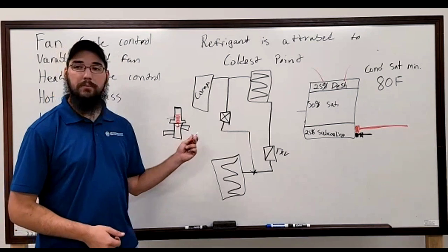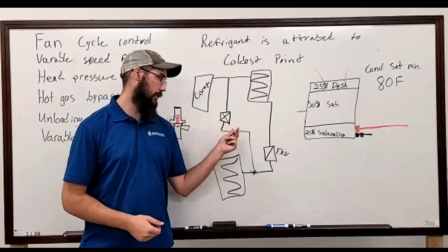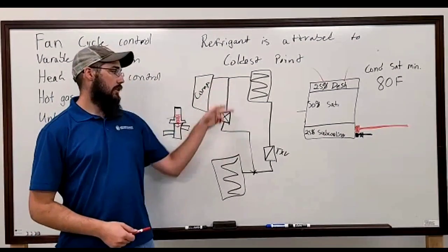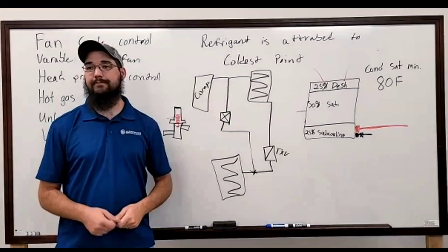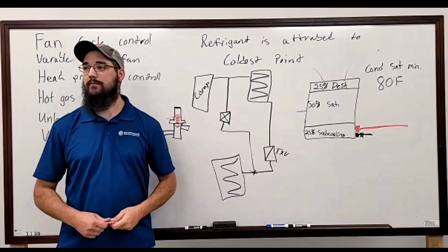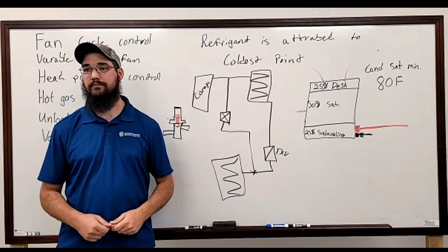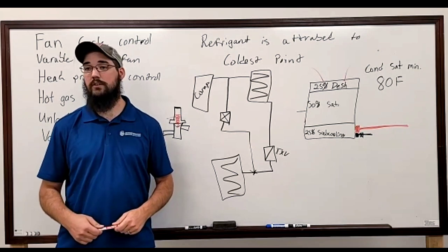So, one of the really easy ways to know if you're in a hot gas bypass state: this little line that comes off, just grab it. See if it's hot. If it ain't hot, then you're not in bypass. You can check.